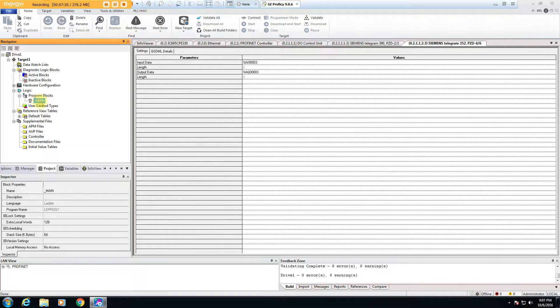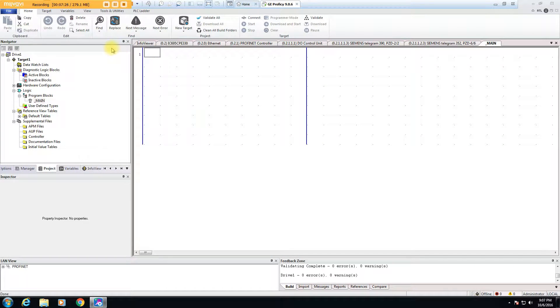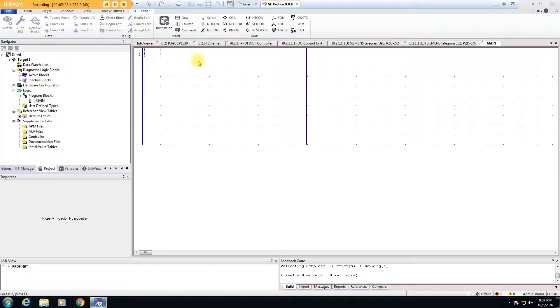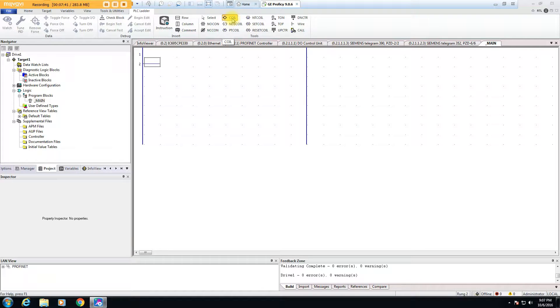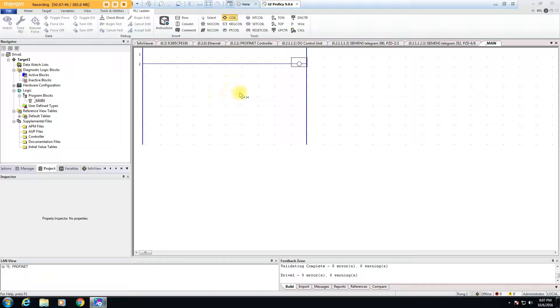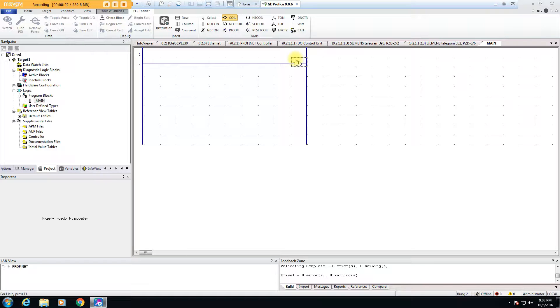With the Siemens drive, you gotta remember for the drive itself you gotta send bit 10 in the control word, which is the first word of the drive. This is a kind of legacy thing, it just tells the drive that the PLC wants to have control. Basically the drive won't send or receive data at all until bit 10 gets set. So before you think you're gonna see anything going back and forth, you gotta have bit 10 set. It's just like when you're doing with the Siemens PLC, it's the first thing that you really need to make sure you set in your program.